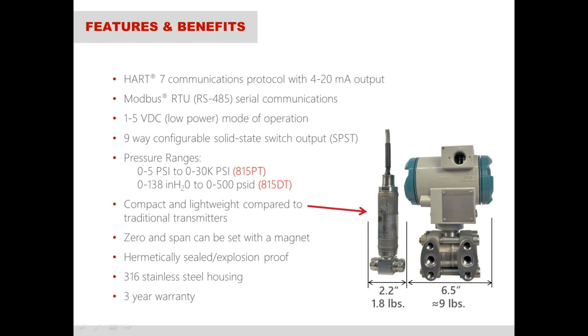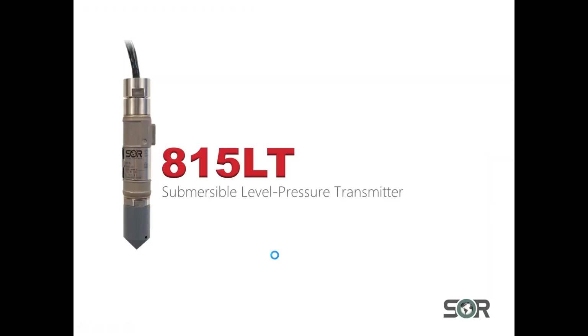Pressure ranges that we offer for the 815 PT, we can go all the way from 0 to 5 psi, remember with a 5-to-1 turndown, all the way up to a 30,000 psi pressure transmitter. We can do absolute pressure ranges as well as vacuum pressure ranges if you need us to. The 815 DT goes from 0 to 138 inches of water column all the way up to 0 to 500 psi differential. Now moving on to the 815 LT.